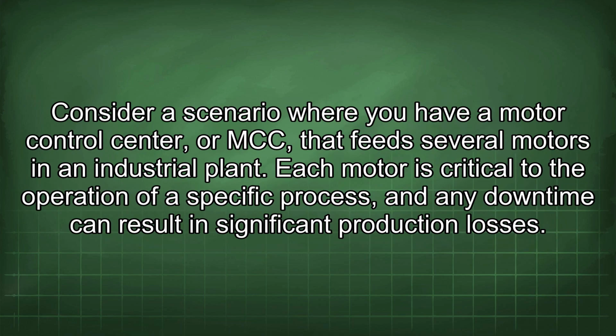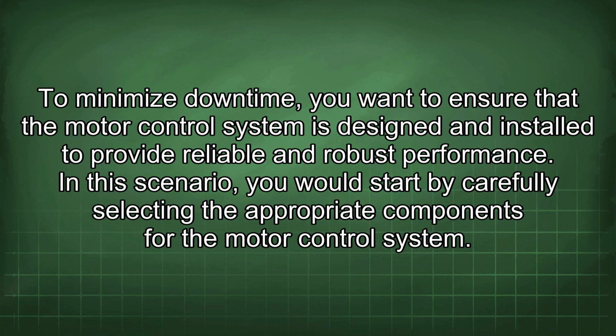Consider a scenario where you have a motor control center, or MCC, that feeds several motors in an industrial plant. Each motor is critical to the operation of a specific process, and any downtime can result in significant production losses. To minimize downtime, you want to ensure that the motor control system is designed and installed to provide reliable and robust performance. In this scenario, you would start by carefully selecting the appropriate components for the motor control system.